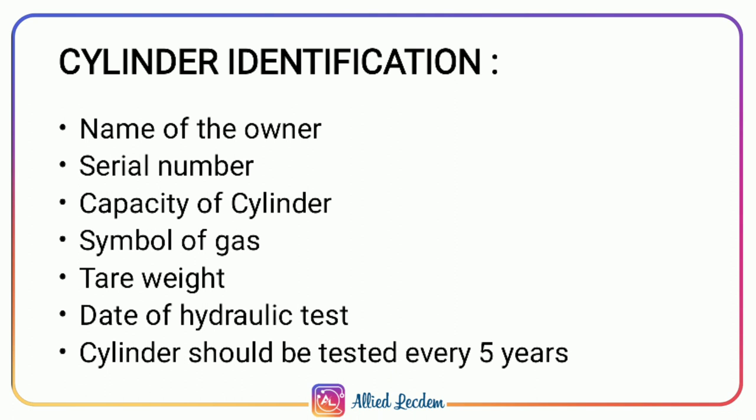While receiving a cylinder, we should check for the following: name of the owner, serial number, capacity of the cylinder, symbol of gas on the cylinder, tare weight (the weight of an empty cylinder without gas), and date of hydraulic test. Cylinders should be tested every 5 years.